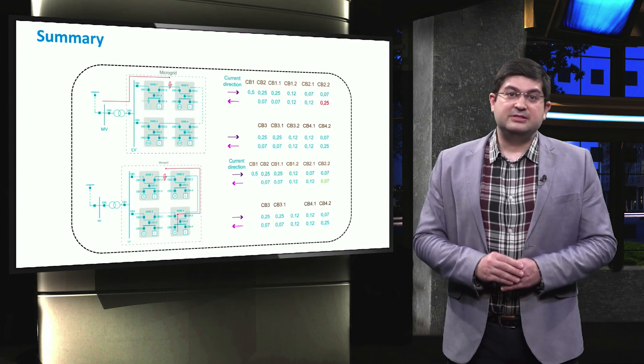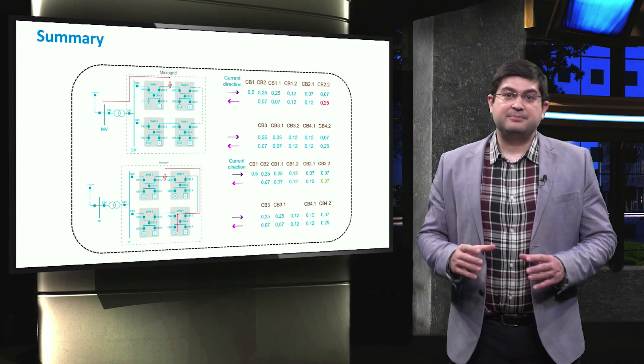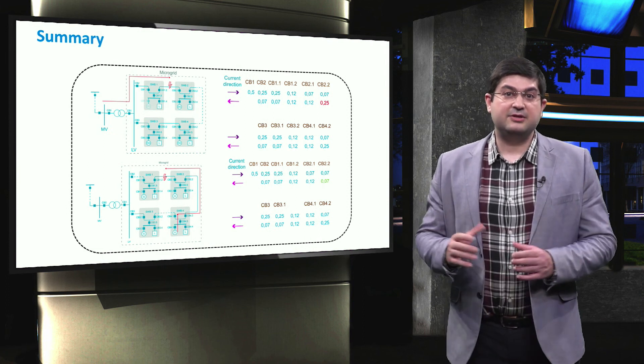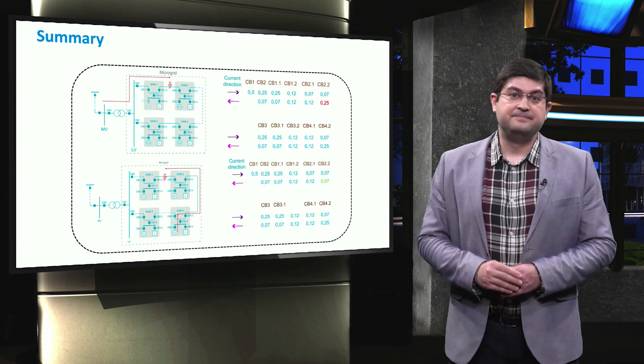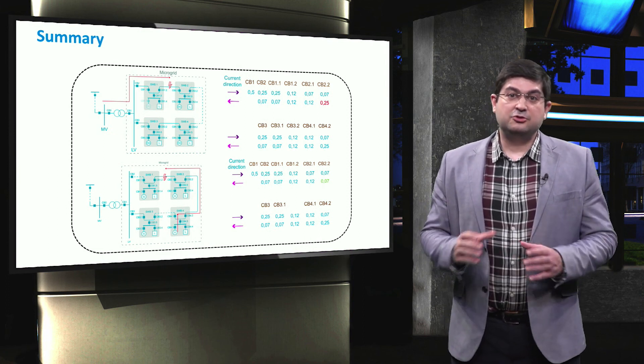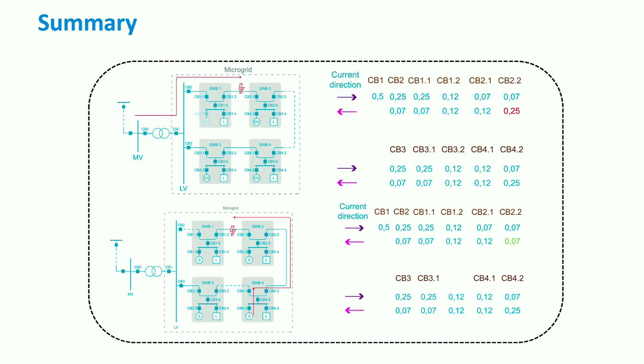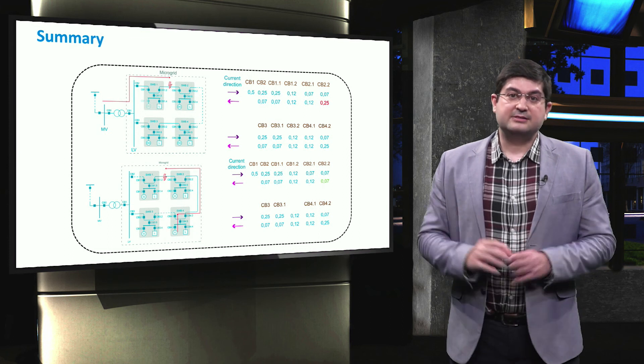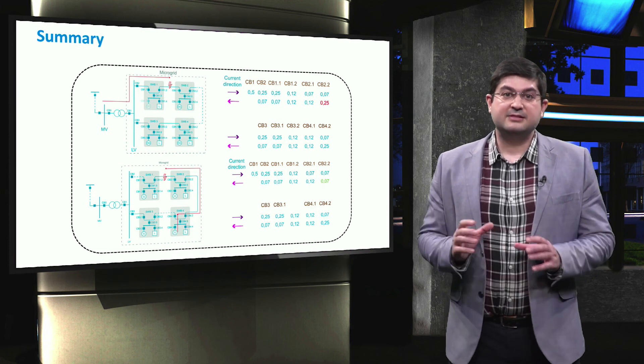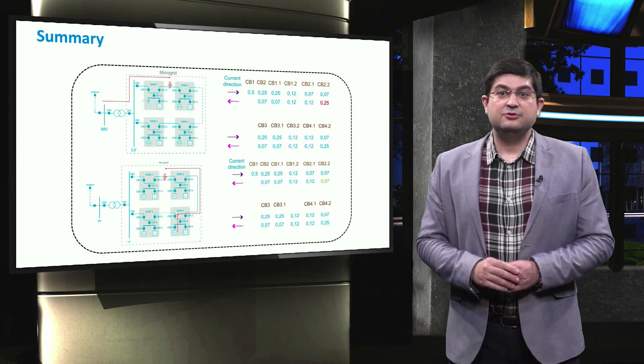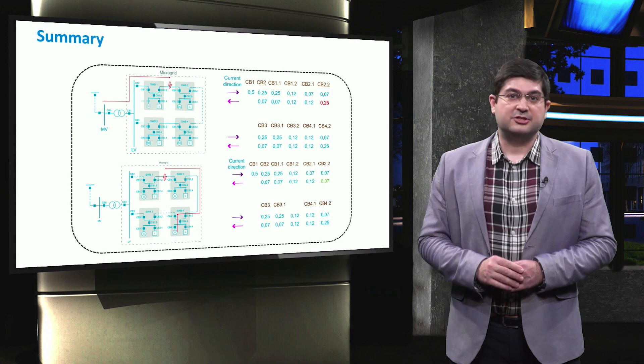In this video, we discussed an example of adaptive protection for a microgrid in the grid-connected mode. We showed that once the configuration of the network changes, a selectivity problem may occur. To avoid this, the time setting of the relays is adjusted using adaptive protection.